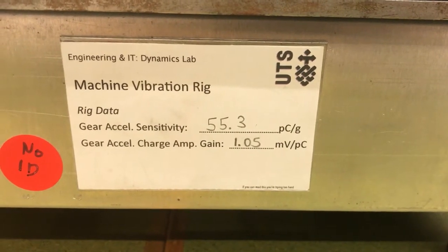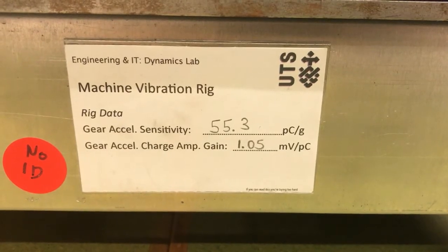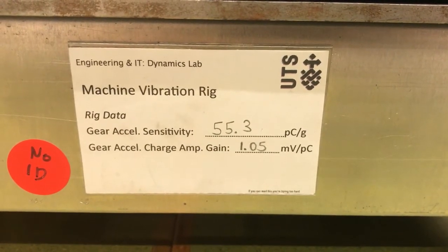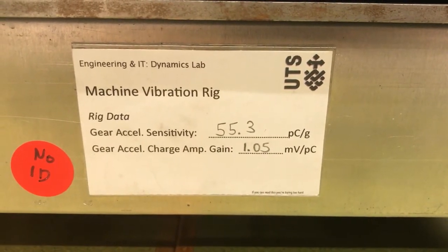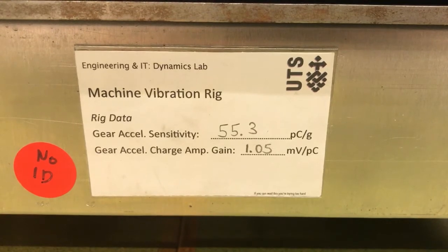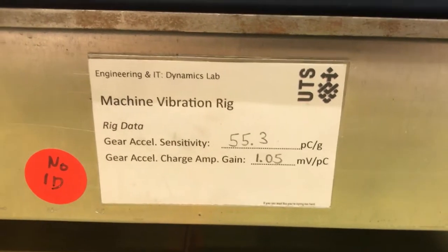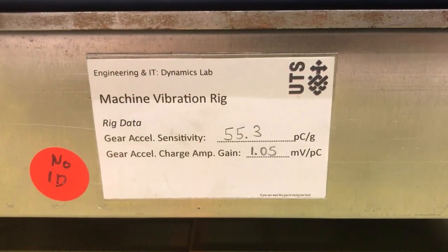I just want to show here that you can see the gear accelerometer sensitivity given in picocoulombs per g of 55.3 and the gear accelerometer charge amplifier gain is given as 1.05 millivolts per picocoulomb. So with these two pieces of information, it's possible to determine the overall channel sensitivity for that gear accelerometer channel.